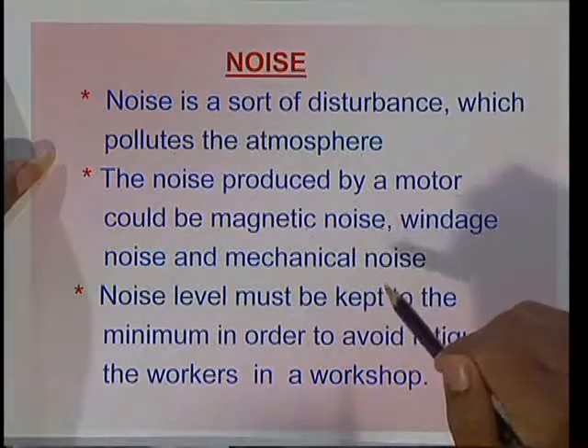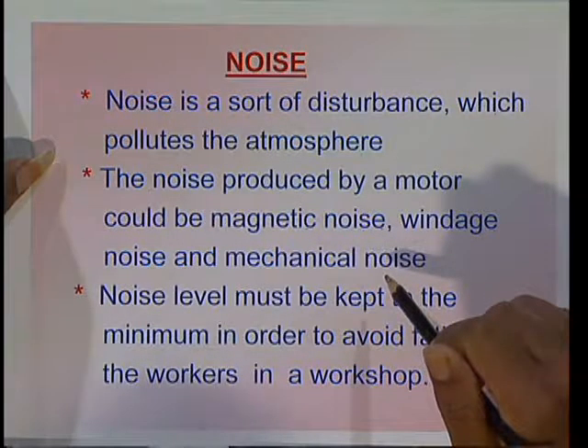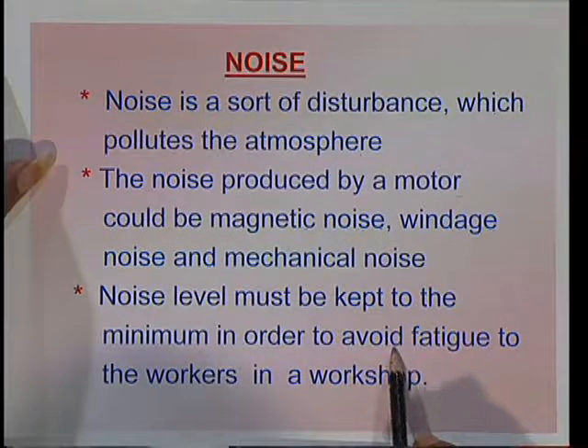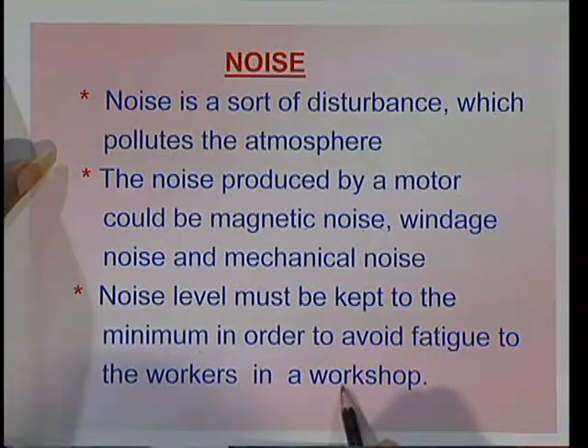Due to the presence of the magnetic core, it gives magnetic noise. Due to the openings for circulation of air, it gives windage noise. Due to the loose fitting of nuts and bolts or worn-out bearings, it gives mechanical noise. Noise level must be kept to the minimum in order to avoid fatigue to the workers in a workshop. Installing less-noise motors in a workshop makes the atmosphere pleasant and increases production.